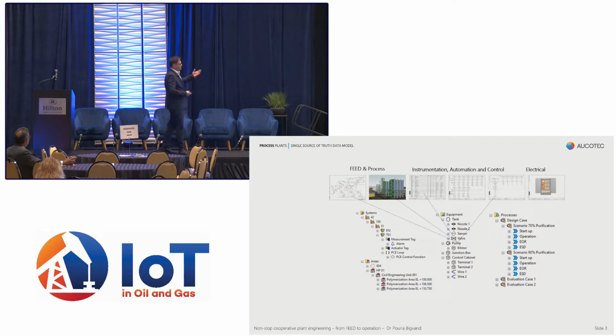So this means that when you have a pump, this pump can have a representation on the P&ID, on the PFD, on the 3D diagram. It really doesn't matter. It's just the same pump with different representations. And based on that, it is impossible that you have inconsistencies between your documentation, because they are just showing the same data from the same object as a single source of truth.